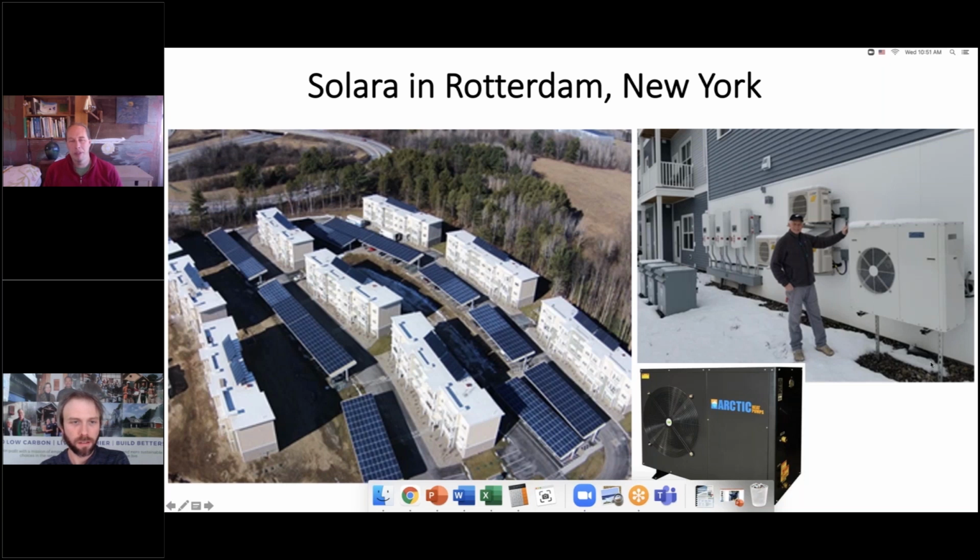Well, that's another problem with CO2, is that it really wants cold water to come in. You can design it for radiant systems, but it wants to do a lift from, say, 40 degrees Fahrenheit up to 140 Fahrenheit. That would be a happy place for CO2, a 100-degree lift. If you ask it to do radiant floor heating, you're asking it to do a lift of 10 degrees, and that makes it very inefficient. It hates that. You want a different type of heat pump and refrigerant to do small lifts. So it's not really designed for radiant floors very well.